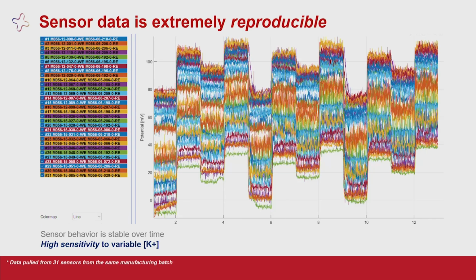Sensor data is also extremely reproducible. We have here in one batch about 30 sensors. Pay attention to the shape of the graphs. They're all the same, just offset a little bit. That's a calibration issue, not a reproducibility issue. Calibration is an algorithm problem. We're going to solve that with our first in-human study, modifying the algorithm to change the calibration.